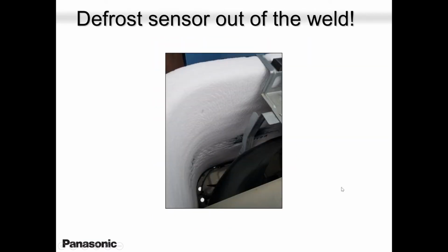So this coil, this picture, I got it recently, and this was not low on refrigerant. When the guy sent me this picture, I told him to open the unit and check the defrost sensor. And right enough, the defrost sensor was out of the well. I don't know what happened, honestly, but the sensor was not in that pipe. There is a well that the sensor goes into, with a clip. The clip was missing and the sensor was out. So after he put the sensor back in the correct spot, and made sure it's nice and tight with the clip, everything is up and running.